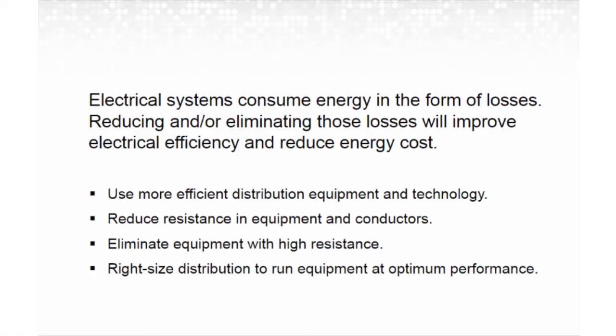And it's prudent for the design team to choose equipment ratings that can provide increases in energy efficiency. Design aspects that we've discussed include looking at resistances and losses within the distribution and within the conductors. We talked about how to size equipment, how to utilize equipment. As it relates to UPSs, how that architecture and how that system's designed and how it's operated all factor in.